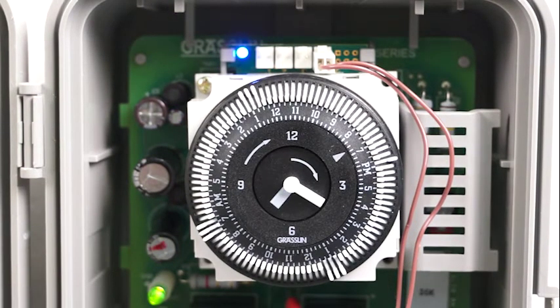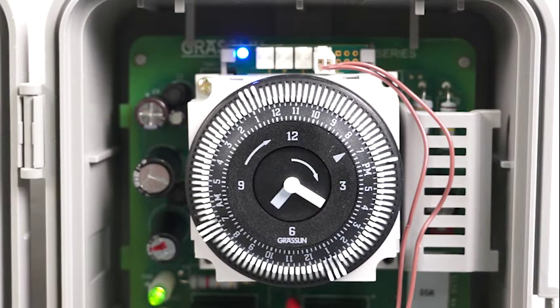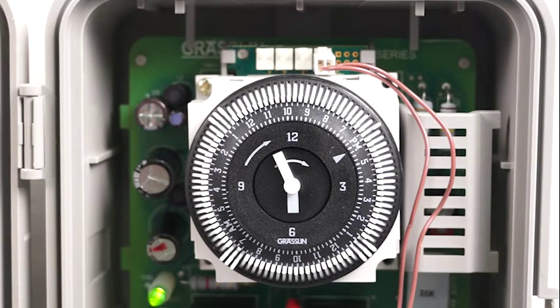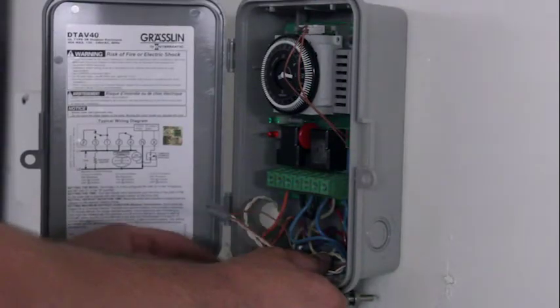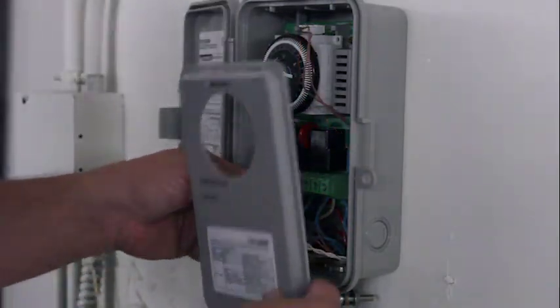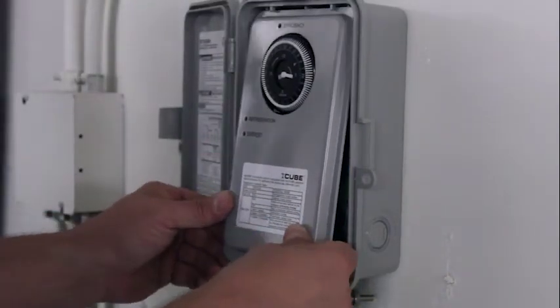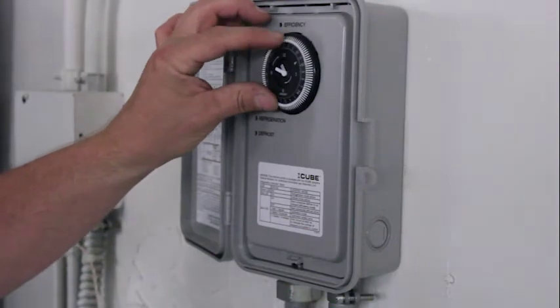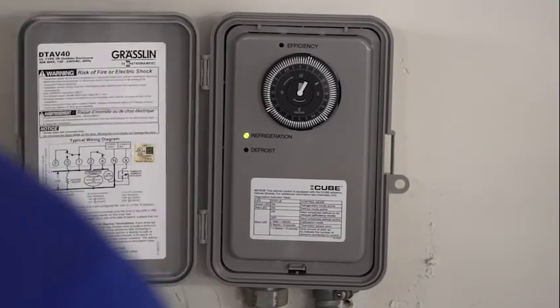When the blue light stays on continuously, the Icube is in efficiency mode. In efficiency mode, the next scheduled defrost event will be bypassed because the evaporator is running at optimal frost-free conditions. When the LED light turns off, the Icube's efficiency mode is off, and a defrost will initiate at the next scheduled event. Now, tuck all of the wires back into the enclosure. Snap the protective insulator cover back into place, and reset the time of day by spinning the dial. There's no need to change the scheduled defrost events. The Icube will now only allow a defrost when needed at the next scheduled defrost.